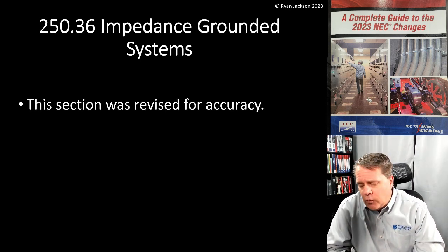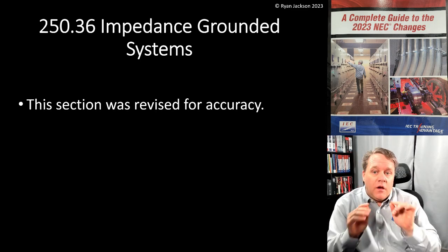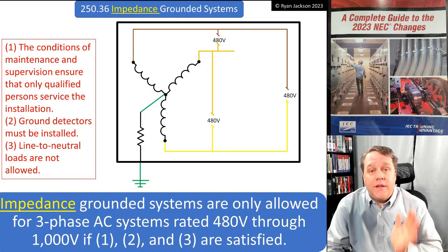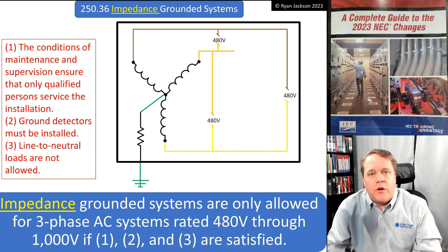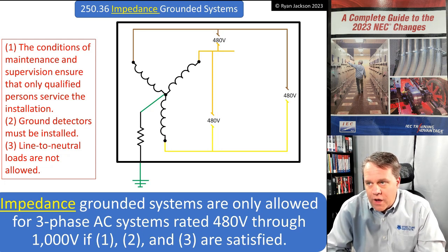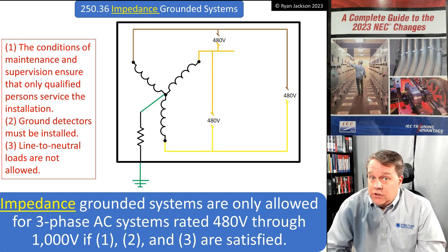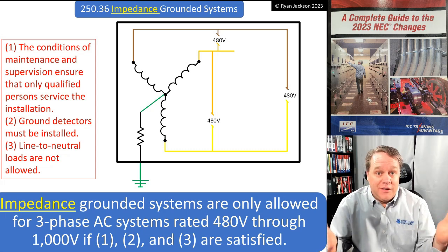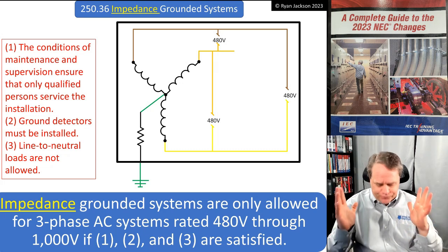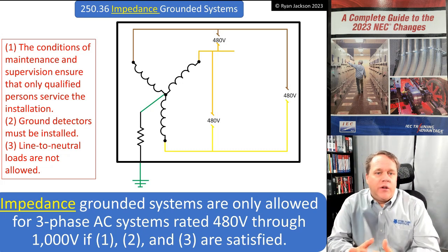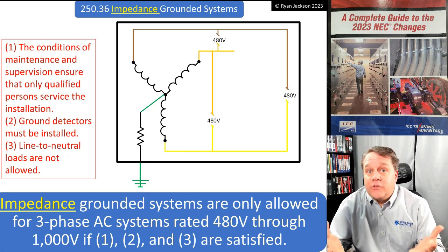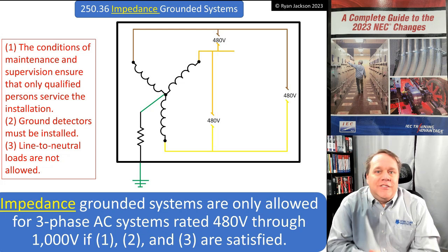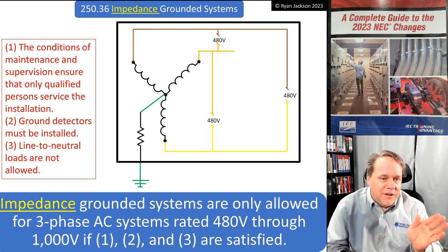First of all, 250.36 used to be called 'high impedance grounded neutral systems.' Well, why does it have to be 'high' impedance? There's certainly low impedance grounding as well. There's high impedance grounding and low impedance grounding, and as far as the NEC is concerned they're all the same - it's just impedance grounding. So right off the bat, calling it 'high impedance' never made sense.